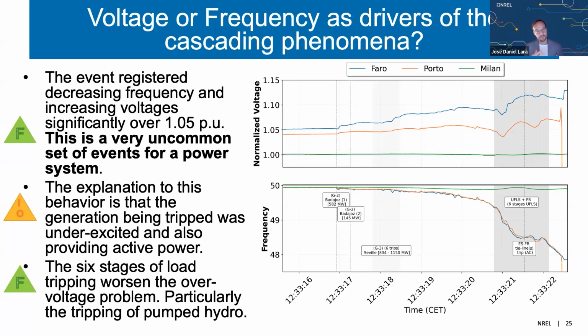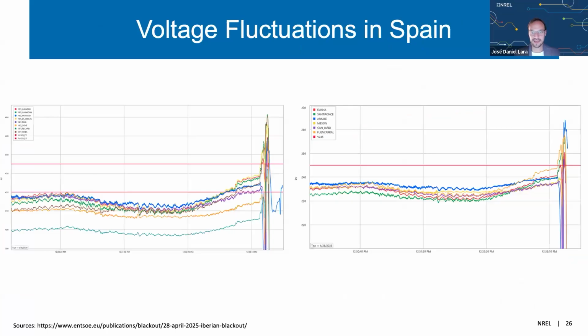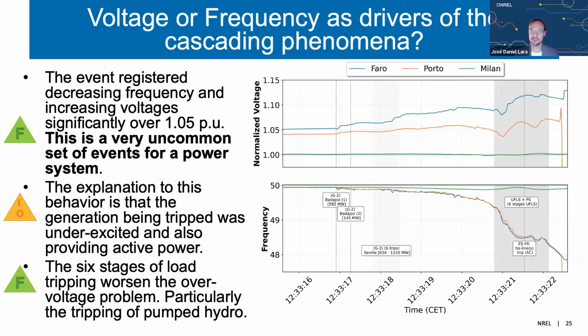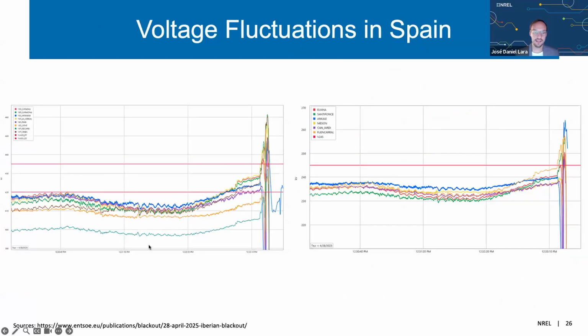So as the voltage starts to rise and trips because of voltage reasons those units, you're losing the active power, but as the units trip, you have a run of voltage going upwards. And again, this plot is from the data that we produce thanks to the INES data. And then this is the detailed ENTSO-E publication that confirms for other several locations in the region the same problem, right? Maybe you cannot see well the timestamp, but this starts around 12:30. You can see the voltages go down and then suddenly start tripping up until we have this runaway of overvoltage that led to the blackout, right?